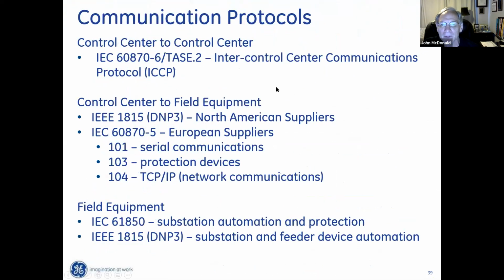In 35 years of doing smart grid standards work - if we look at control center to control center, there's only one worldwide standard for one control center to exchange information with another, called ICCP, Inter-Control Center Communications Protocol. From control center to field equipment, it's either IEEE 1815, which in North America we use a lot, called Distributed Network Protocol 3, or if it's a European supplier, IEC 870-5, 101 for serial communications and 104 for network. Then within the field, IEC 61850 is the worldwide standard, no question, for substation automation and protection. But in North America we still use a lot of DNP3, or IEEE standard 1815.